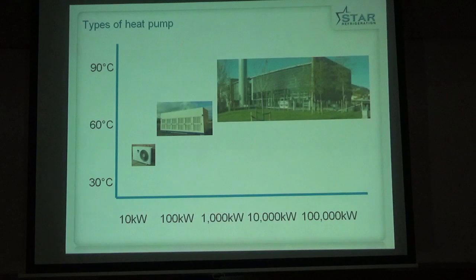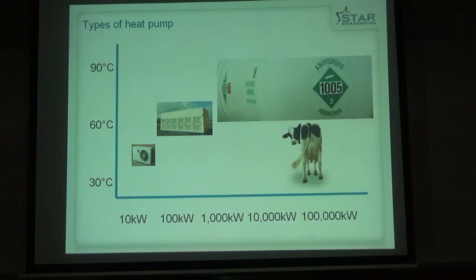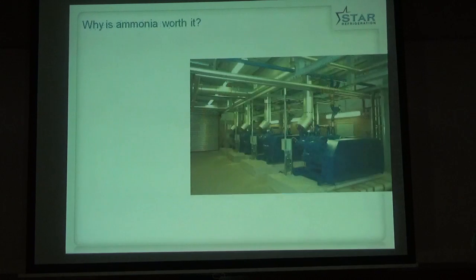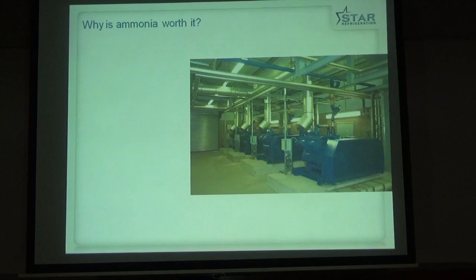And this is where the ammonia comes back in. I mentioned ammonia at the beginning. Ammonia is a bit like standing around the wrong end of a cow. It's kind of smelly, unpleasant. But it's a very, very common industrial chemical. It's produced to the tune of about 160 million tons a year, most of which is used in agriculture and is just injected into the farm fields. And about 1% of that production is used for refrigeration applications. So here's a typical ammonia refrigeration plant room, all fairly standard stuff.